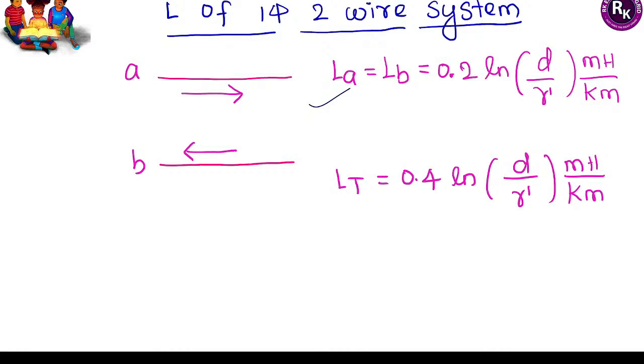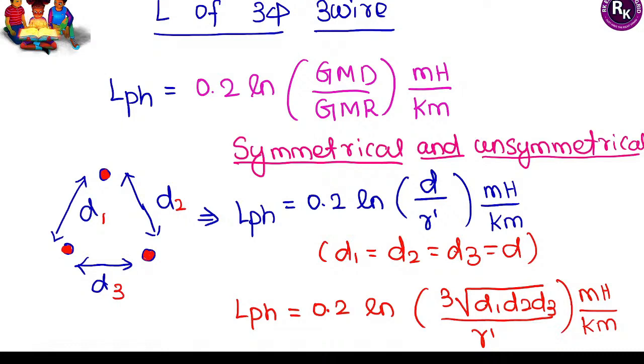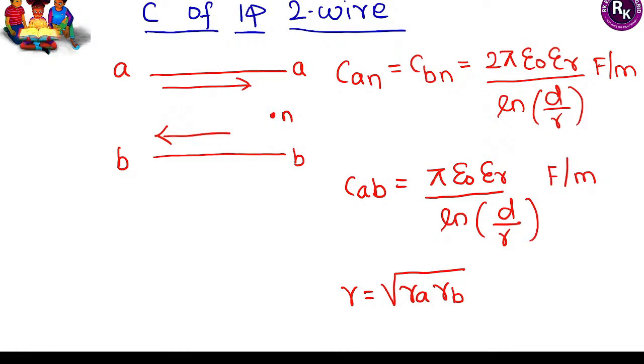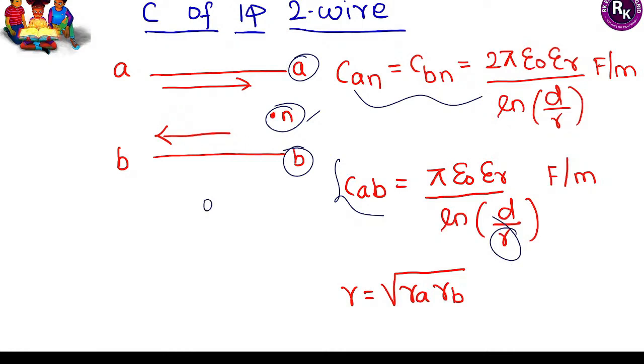For a single-phase two-wire line, inductance formulas are written separately for phase A, phase B, and the total inductance. For three-phase lines, the general inductance per phase is calculated differently for symmetrical and unsymmetrical configurations. For capacitance: single-phase capacitance per phase (line to neutral) and line-to-line capacitance formulas are given. For capacitance calculations, the factor 0.7788 is not considered because there is no internal flux for capacitance — use the actual radius directly.